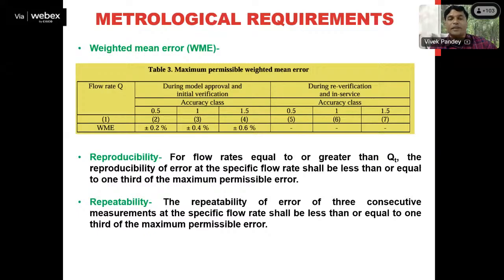Suppose we have taken 5 readings to check its consistency. Whenever we are taking these 5 indications, we should ensure that the conditions remain consistent. That means the user should be the same, and the environmental parameters should be the same. There shouldn't be any change in the density of the gas, in the temperature of the environment or the laboratory, or in the humidity, and there shouldn't be any considerable change in the pressure of the gas. And yes, the most important thing, the flow rate of the gas should be the same. If we have decided to check the consistency at 200 liter per hour, it should be 200 liter per hour for all the readings.